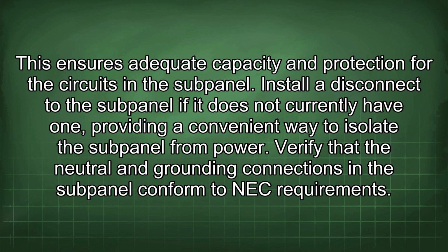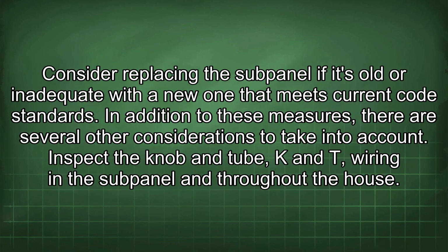Install a disconnect to the subpanel if it does not currently have one, providing a convenient way to isolate the subpanel from power. Verify that the neutral and grounding connections in the subpanel conform to NEC requirements. Consider replacing the subpanel if it's old or inadequate with a new one that meets current code standards. In addition to these measures, there are several other considerations to take into account.